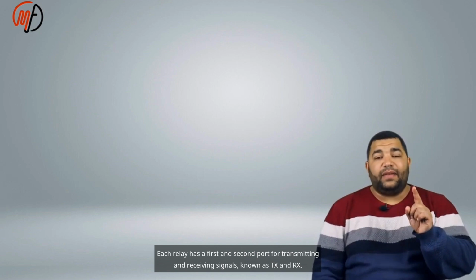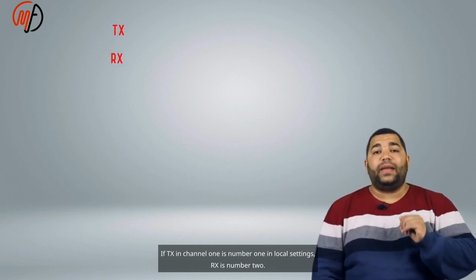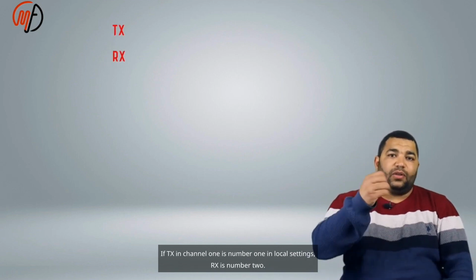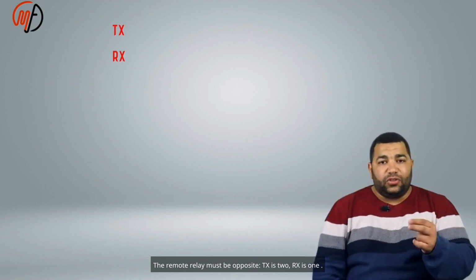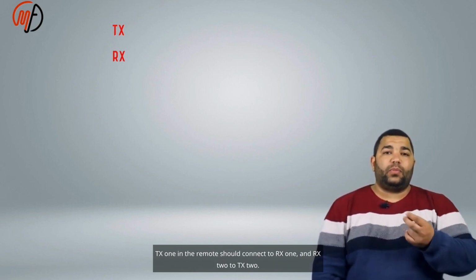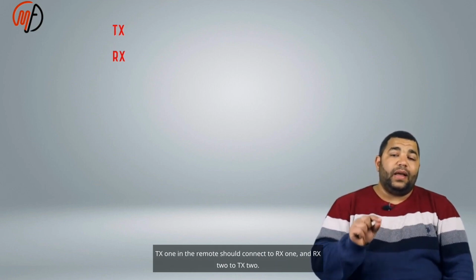Each relay has a first and second port for transmitting and receiving signals, known as TX and RX. If TX in channel 1 is number 1 in local settings, RX is number 2. The remote relay must be opposite: TX is 2, RX is 1. TX1 in the remote should connect to RX1, and RX2 to TX2.